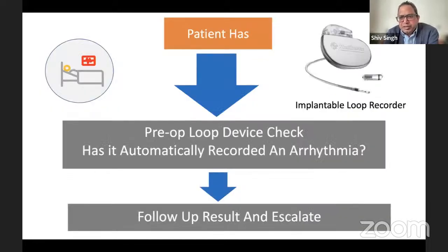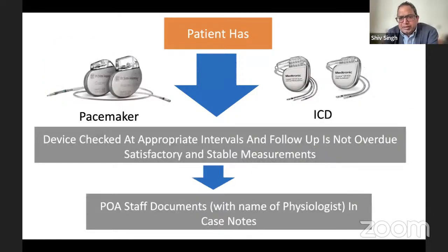If the patient has an implantable loop recorder, or the loop, then we need to know if this has been recording some kind of arrhythmias which could be significant. So we need to follow up with the results and escalate accordingly. If the patient has a pacemaker or ICD, then you need to know when the device was last checked, and whether the patient is due for another check. And this has to be documented in the notes, along with the name of the physiologist who has done the check, or where it was done.